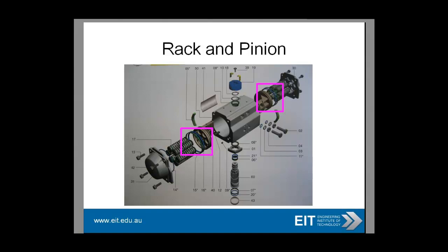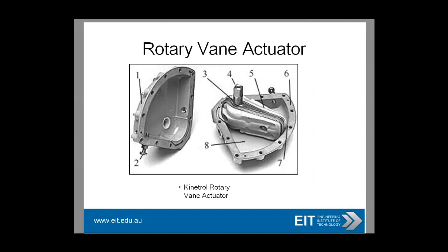These aren't the only pneumatic actuators. You can also get a rotary vane actuator, which is a good alternative to piston actuators, especially where high loads are encountered. There are no links or gears, but it is bulky and heavy. Maintenance problems occur more frequently than you'd like. It's a quarter-turn actuator — you can see the small amount of turn. You can get a fail-safe operation, though it occurs in a very limited range.